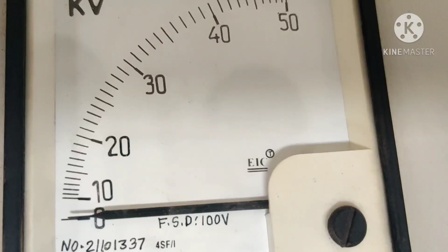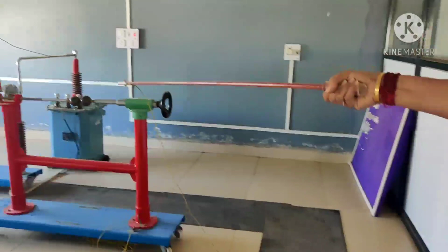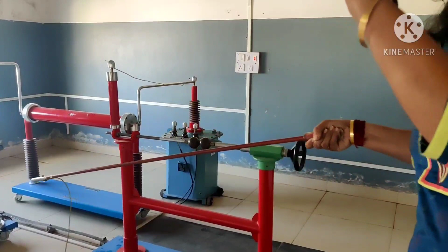Now once we have done it for 5 mm gap length, we know 12 kilovolt is the breakdown voltage. Our work now is to vary the gap length to 10 mm. So we open the door, and we make use of this ground rod, hold properly the glass head, and touch this. These are the conducting parts. Touch this. Now all excessive electrons are moving towards the ground, so now we are all safe.